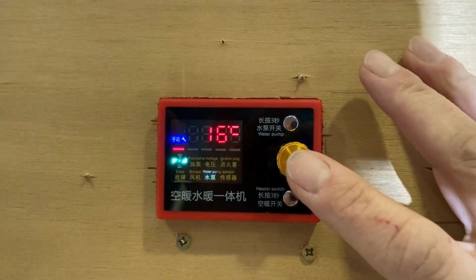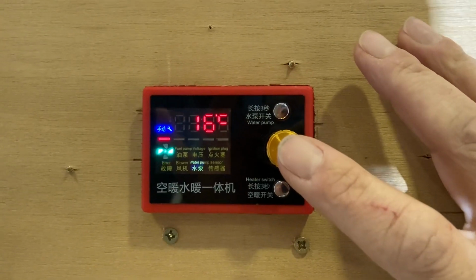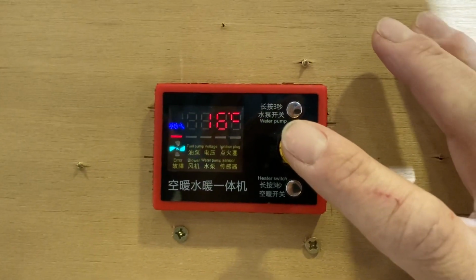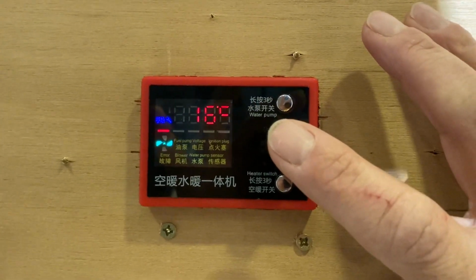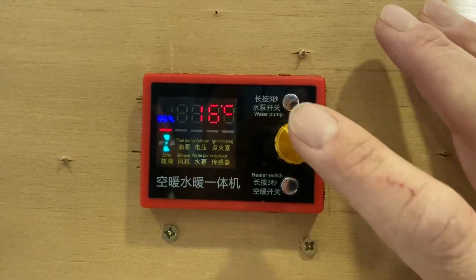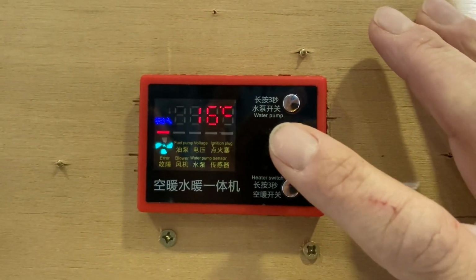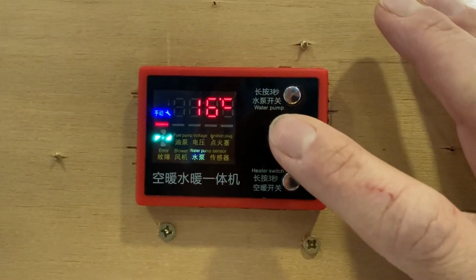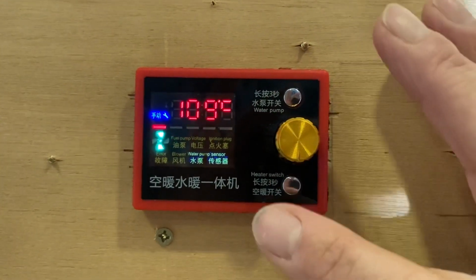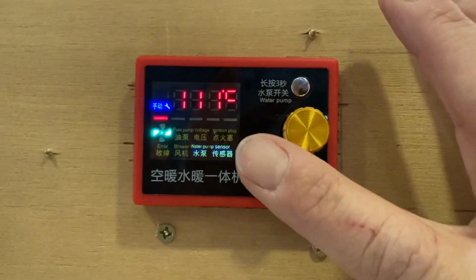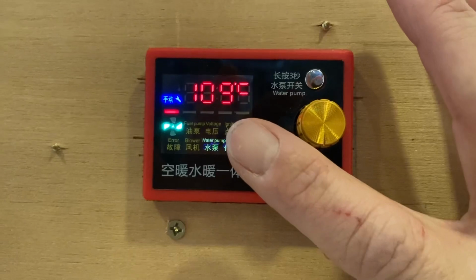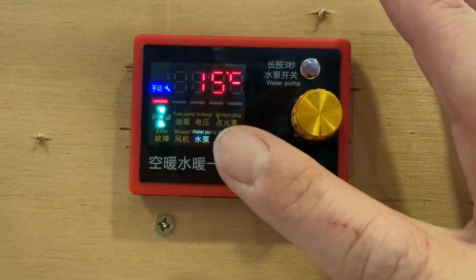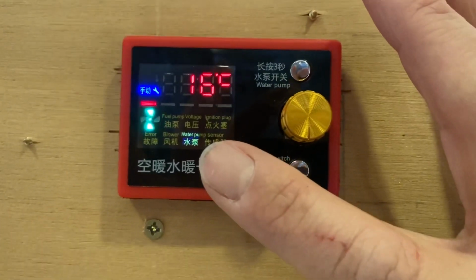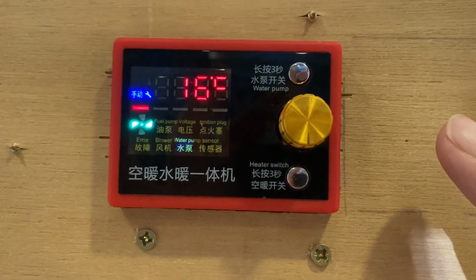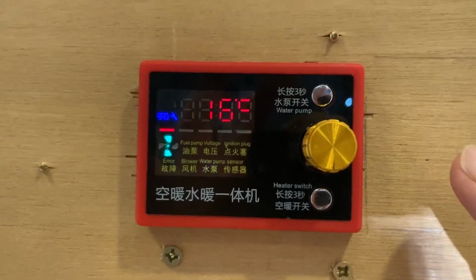The fact that it's cold outside definitely has a bearing on things, because when I did the second bench test of the redesigned version, it was running at 160 degrees, but it was warmer in the garage when I did it. It's 0 degrees outside more or less, and when I check the temperature of the gasket, it's operating at 110. Now the pump's on - it'll jump up another 25-30 degrees if I turn the pump off automatically, because the water system helps cool the machine down. If you turn the water system off, the machine gets hotter.